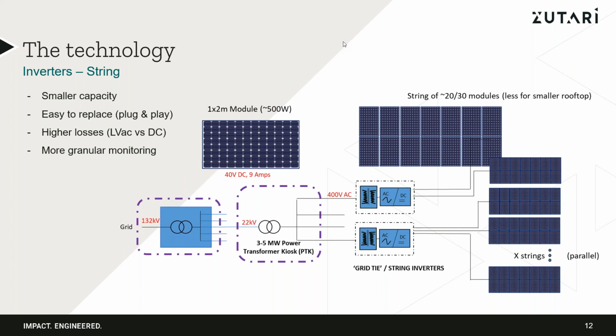The drawbacks, I think, with string inverters are that they can get high losses because you've got more AC than DC. DC is better for loss. And as much as I said there's a great amount of control that you can get out of these string inverters, you still need to trench more, and you need to install more comms cables to all the inverters. And when we're talking about processes with grid code compliance and REtech, we're now looking at a much more distributed plant for the power plant controller to control the output of. So that PPC needs to have a little more programming to enable it to operate a plant, especially a large plant with a very large number of string inverters.